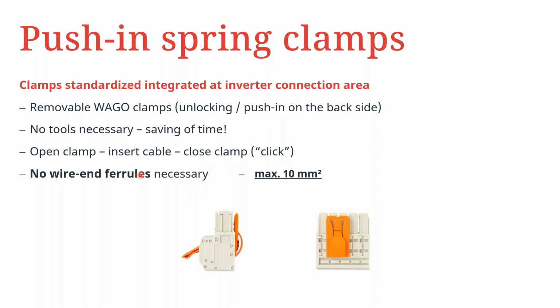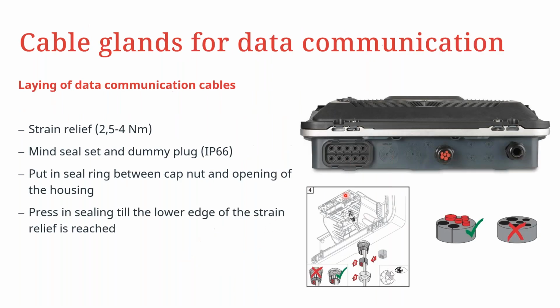In terms of the cables, you do not need to use ferrules, and the maximum cable cross section that can be used for the GEN24 Plus is 10 millimeter square. When it comes to data communication, we have the provided cable gland here. When you want to fit the datacom cables, for example an internet connection to a router if you're not able to use the Wi-Fi connection, you need to remove only the knockouts that are going to be used. As you can see in these illustrations, you should not remove all the knockouts from these cable glands, because that would expose the inverter to dust or other kinds of ingress that could affect the connection area.